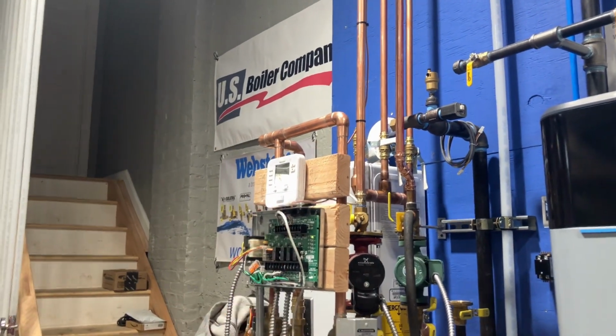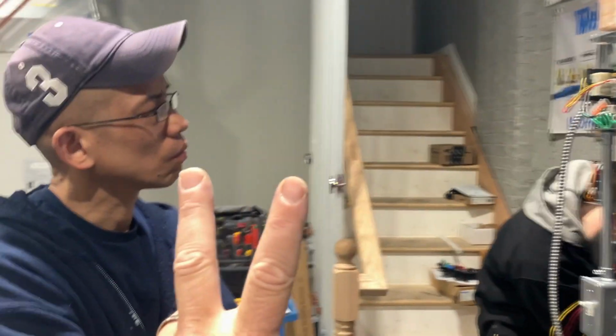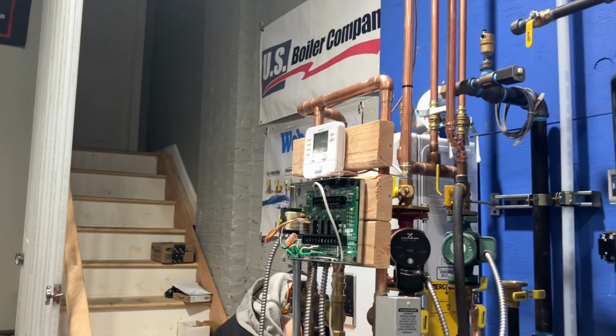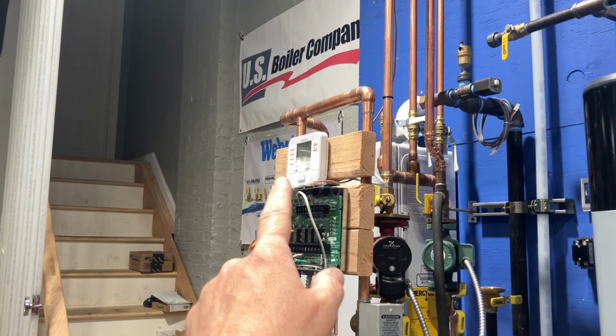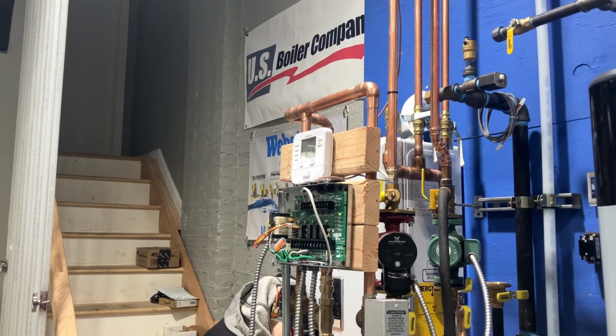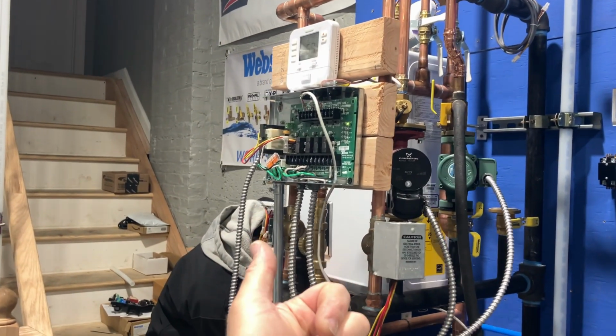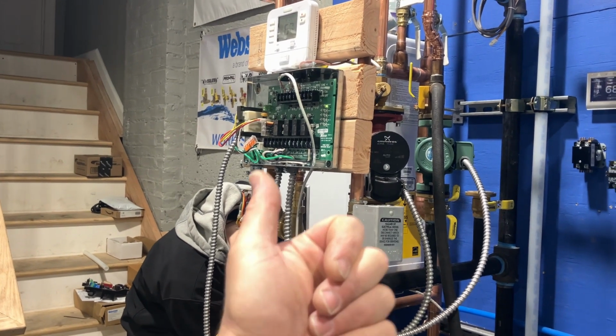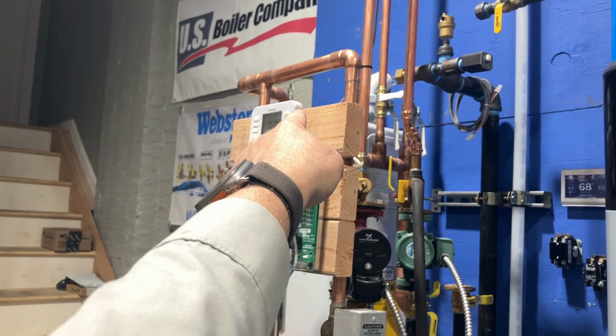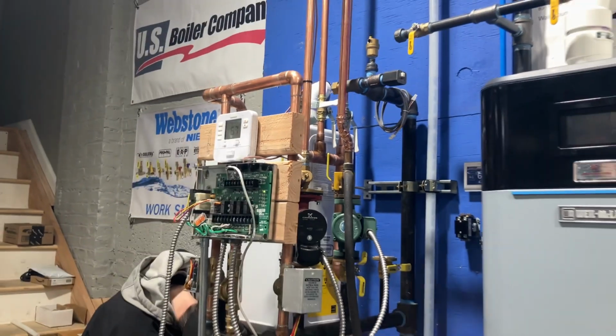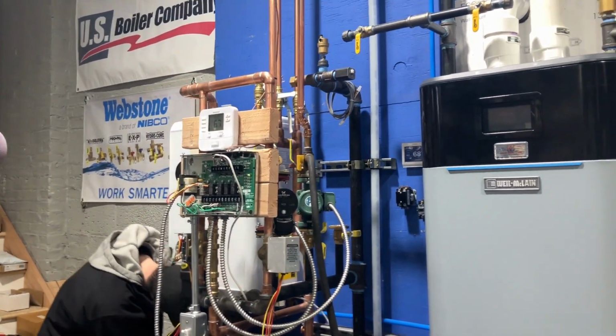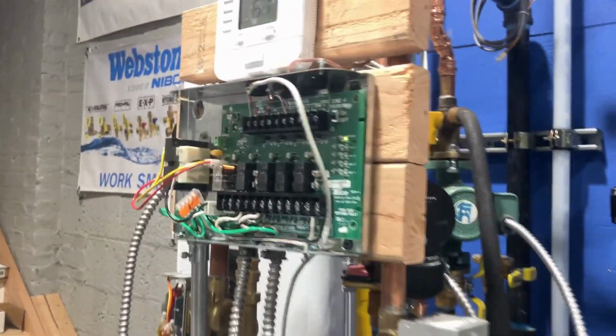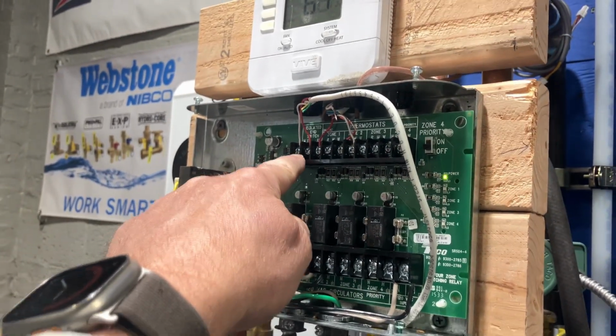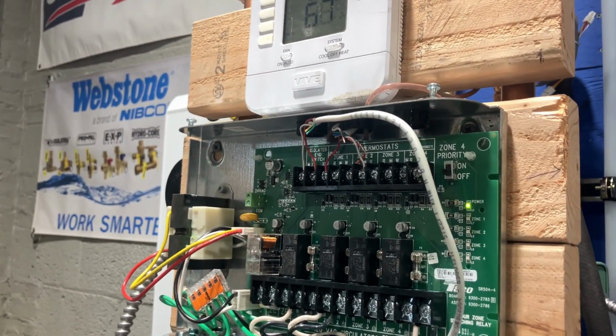And sometimes you have to remove that jumper when you have a 2 transformer system. That jumper is in place with a 1 transformer system when you're using heating and cooling on the same thermostat. If you have a separate air conditioning transformer and a second heating transformer, you can't keep that jumper there because you'll blow out something, either both transformers, 1 transformer, or the other. So to test that, remove the wires. Remove one of the wires, or both wires.